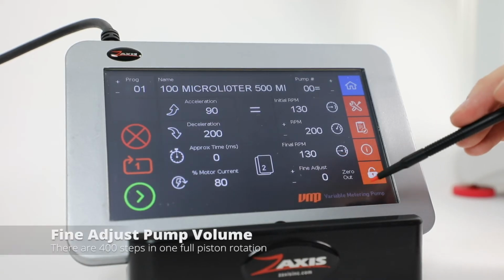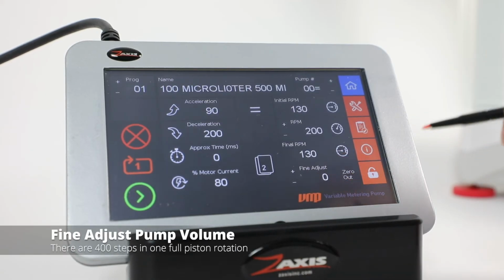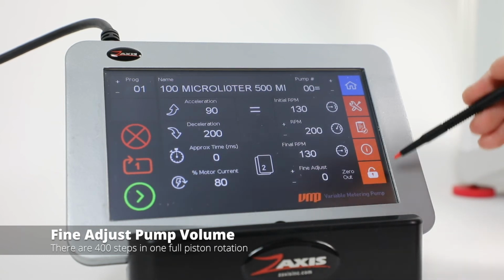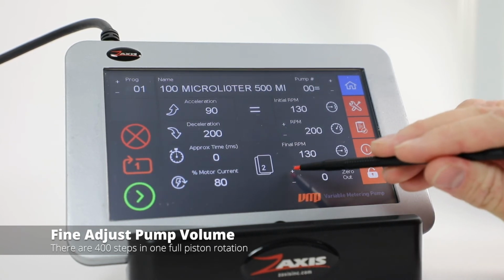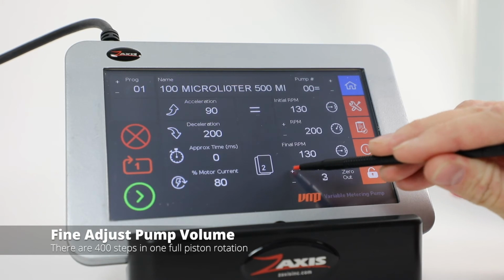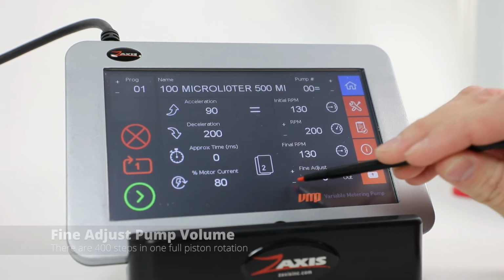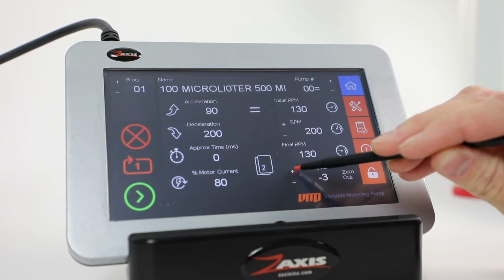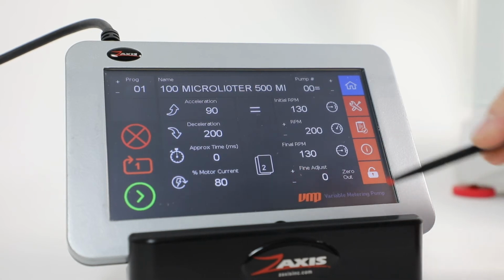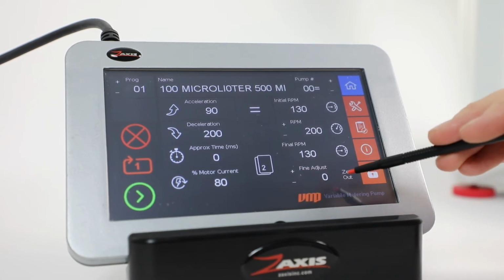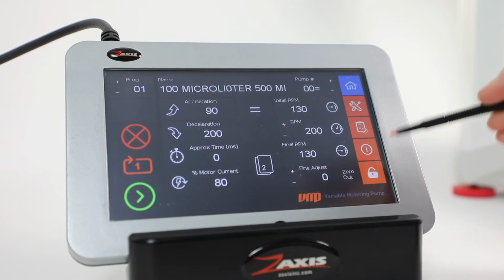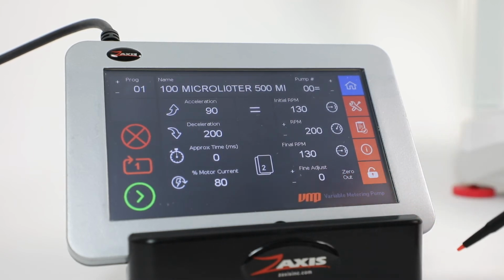So here we have the fine adjust button. If the pump volume is off by just a little bit, you can come in here and you can adjust it using these plus and minus buttons. And you can adjust it up or down, and that should get you closer to your desired volume. This will not save though, so anytime you adjust the pump, it will go back to 0, and you'll have to re-enter the fine adjust.